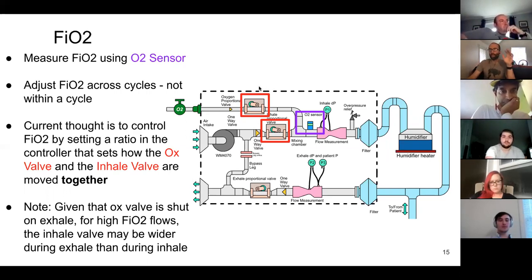But what that means is just taking the two extremes. 100% FiO2, only this valve is open, and we're going to close loop control this valve position to get the patient pressure that we're trying to hit, essentially, right? Everything we do is pressure controlled. To get 21% FiO2, or 100% air, this valve is going to stay fully closed, and we're going to close loop control this valve to get the pressure we're trying to hit. At any point in between, we're going to add those two modes together, but we're not going to try and control FiO2 at the same time as we're controlling pressure.